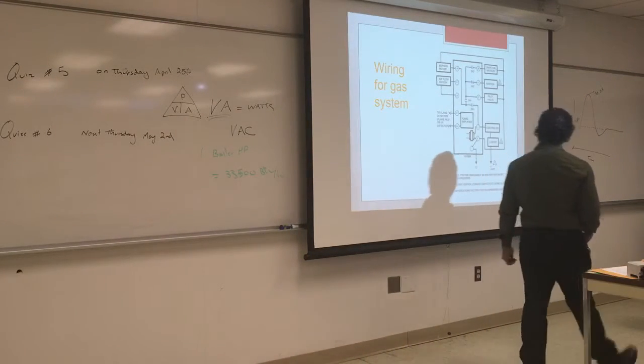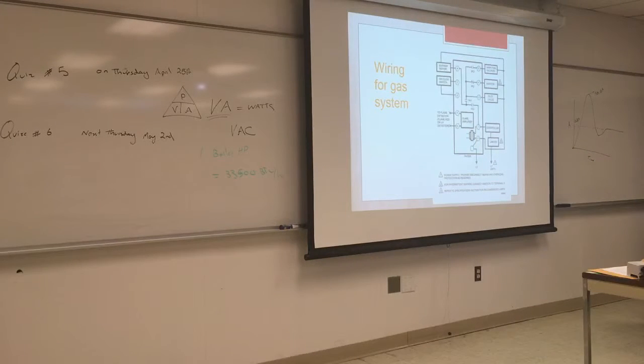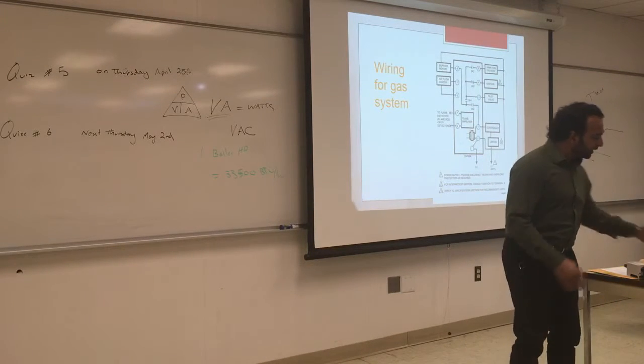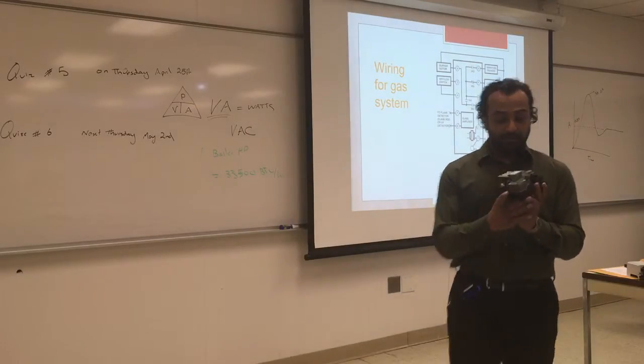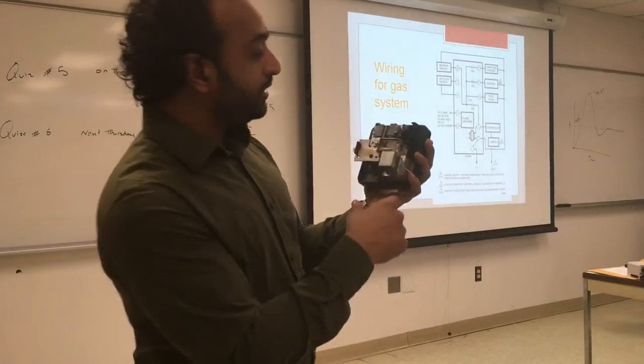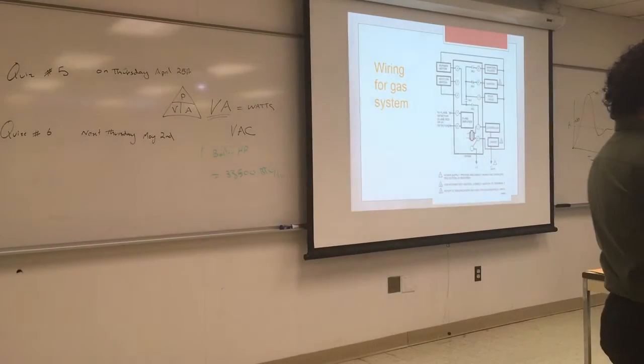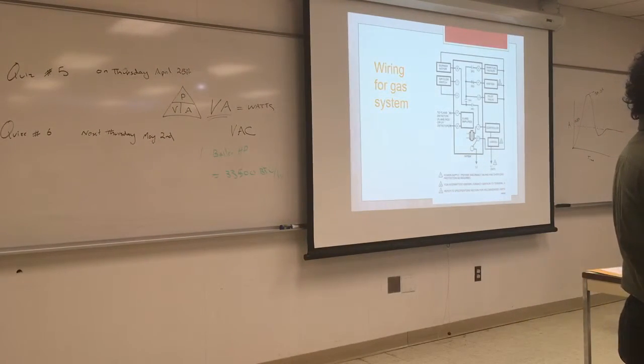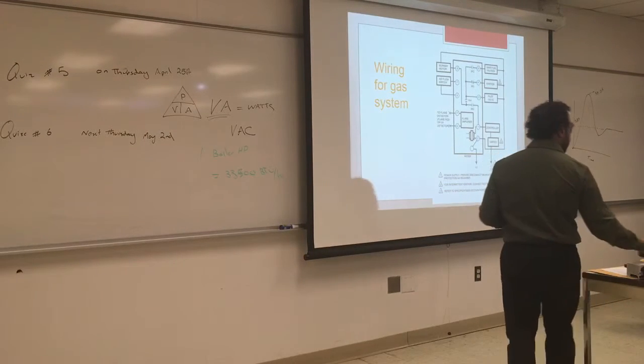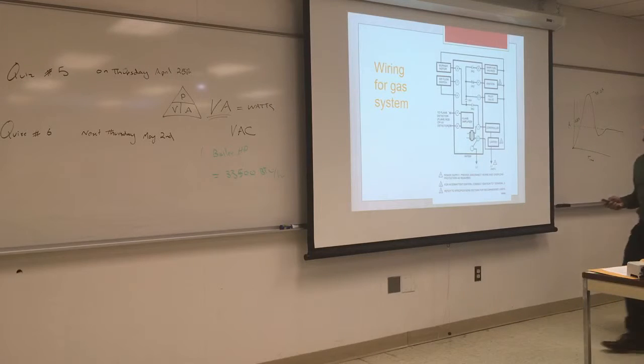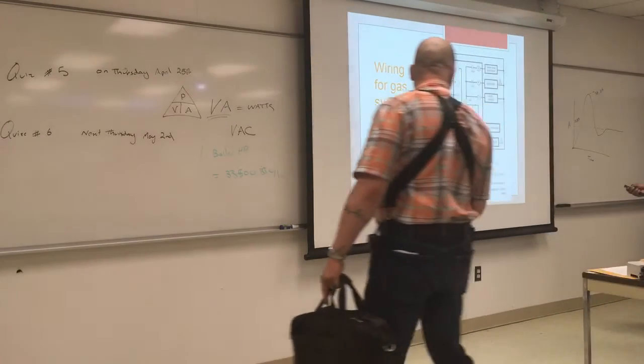So they can be wired for either gas or oil. And probably by now you are very familiar with this wiring. It looks like very typical Honeywell wiring. They have terminals again, and if you look closely here, I'm going to show you with the camera, there are terminals. Those terminals should be solid and should never be changed, and you can alter them based on the type of fuel you have in the burner. So burner motor, similar thing. Again, neutrals come in on one line. Main fuel valve, ignition, pilot valve, controller or limits.